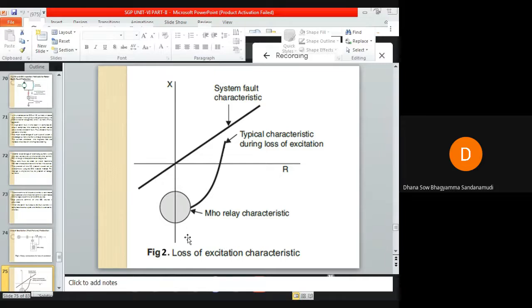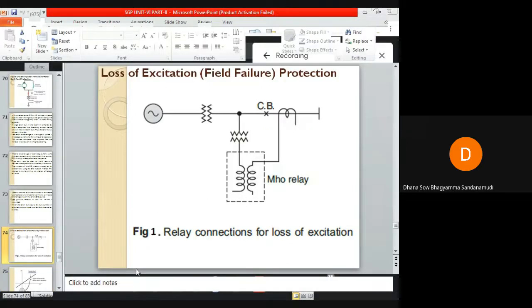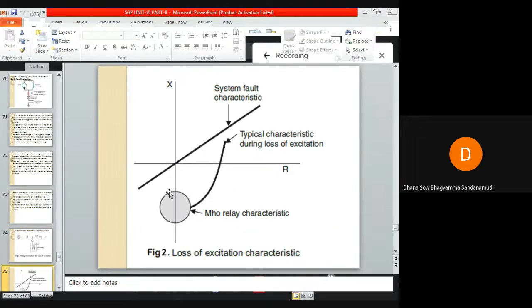This characteristic shows us that whenever the impedance measured by this offset Mho relay lies within this circle, the relay will operate. When the characteristic lies beyond this circle, the relay will not operate, as in Mho relay operation. So whenever loss of excitation occurs, the relay characteristic will swing into this circle, and then the relay will operate.